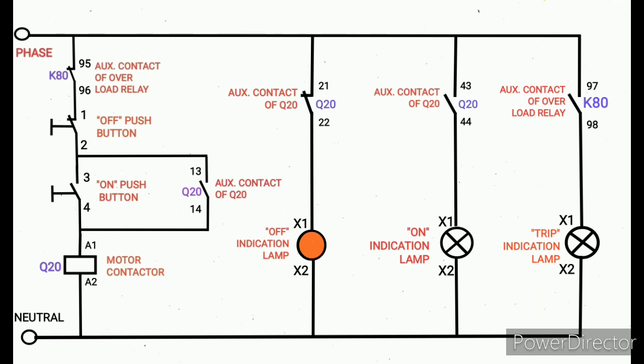This is the off indication lamp, because that auxiliary contact of Q20 21-22 is NC. The phase directly comes to this lamp. That will glow. Now I press the button. The motor contactor coil got supply, means that Q20 got pickup.